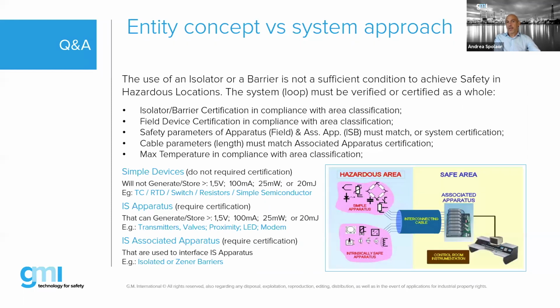We see here that there can be simple devices—thermocouples, RTDs, switches—that don't need certification. Others require certification. In this case, certification is required when certain values are higher than a given threshold: if the voltage is higher than 1.5 volts, higher than 100 milliamperes, or 25 milliwatts, or 20 millijoules. If any of those is higher, the unit needs to be certified; it cannot be considered a simple device.